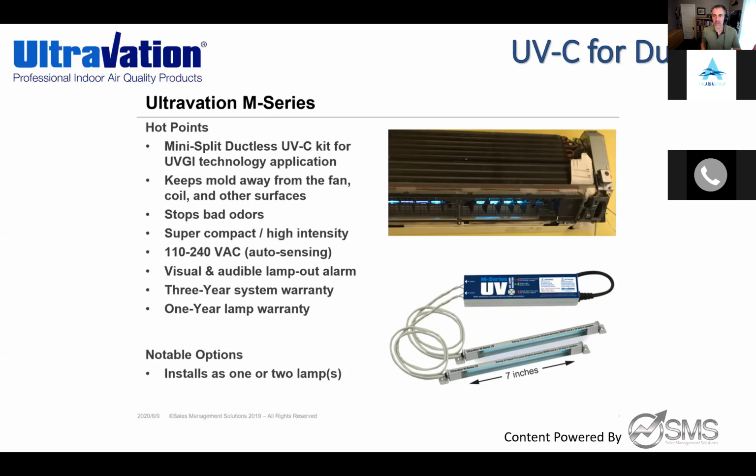You get in there and clean everything, but if you don't want growth coming back in that head, and let me tell you, I saw all kinds of black stuff up inside their heads at their shore houses. So I said, get this clean, and then let's get these UV kits installed, because this will at least help inhibit the growth from happening inside those heads. And I gave you a bunch of cut sheets on those.